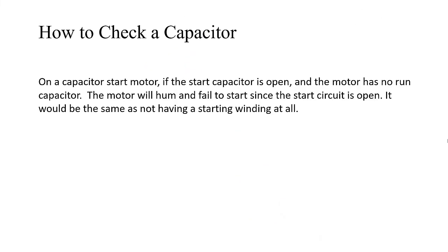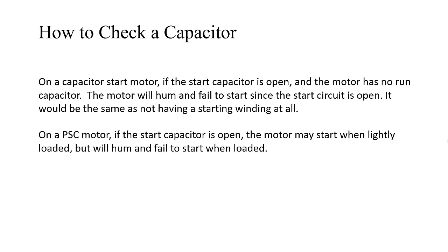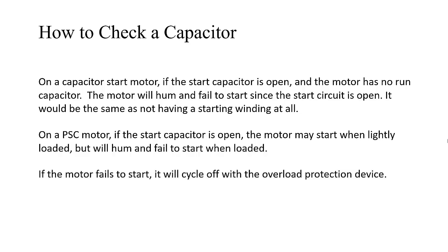On a capacitor start motor, if the start capacitor is open, the motor has no run capacitor. The motor will hum and fail to start since the start circuit is open — it would be the same as not having a start winding at all. On a PSC motor, if the start capacitor is open, the motor may start when lightly loaded, but will hum and fail to start when loaded. If the motor fails to start, it will cycle off with the overload protection device.